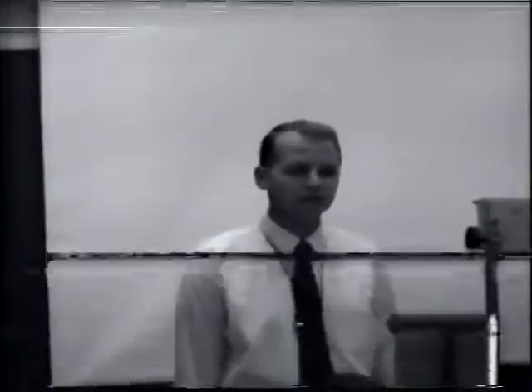Might go over those briefly. I've listed them for 3 voltages that we are using in the majority of our work: 15 kV, 69 kV, and 161 kV. At some of the higher voltages, 345, we haven't gotten the degree of standardization in the industry yet. But at these voltage levels, these figures are accepted as standard for the minimum electrical clearances. And I think most of them are self-explanatory.